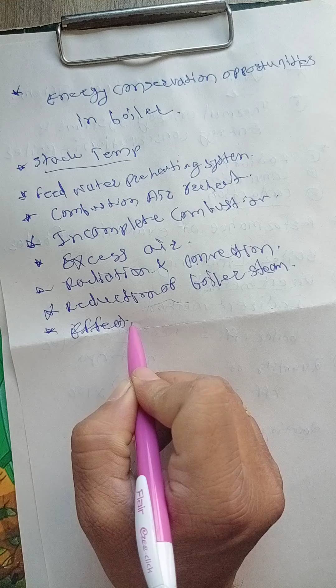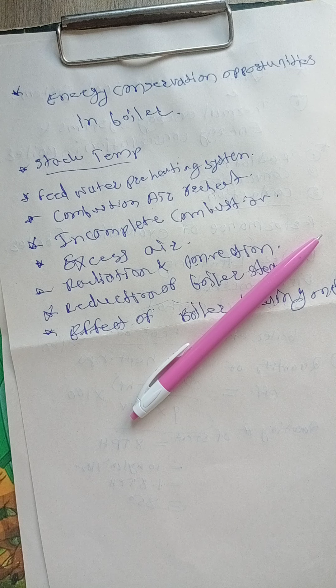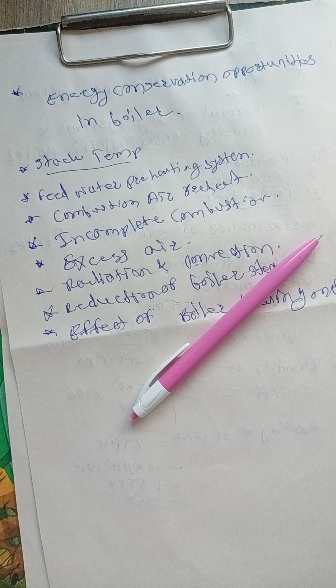Next, effect of boiler loading on efficiency. The maximum efficiency of a boiler does not occur at full load, but at about two-thirds of the full load. If the load on the boiler decreases further, efficiency also tends to decrease.